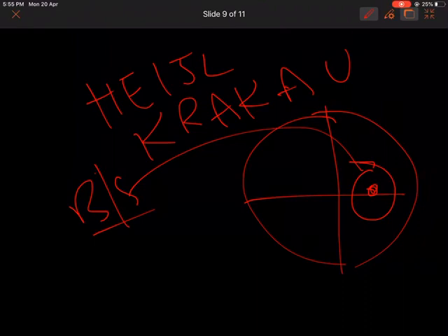When the patient was fixing here, this was the blind spot and he should not be detecting. If the patient moves his eye, is inattentive, and has fixation loss, and his fixating point has reached here, his original blind spot will reach here. Now the HFA field analyzer considers the original location as the blind spot and throws the stimulus here to detect the fixation loss.